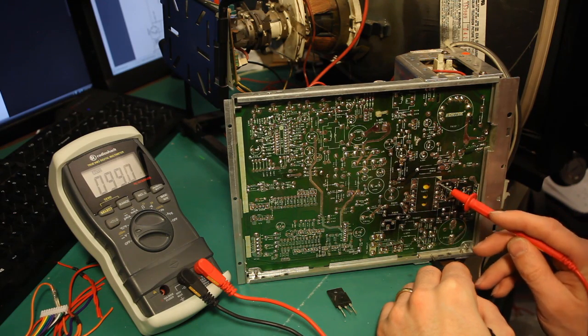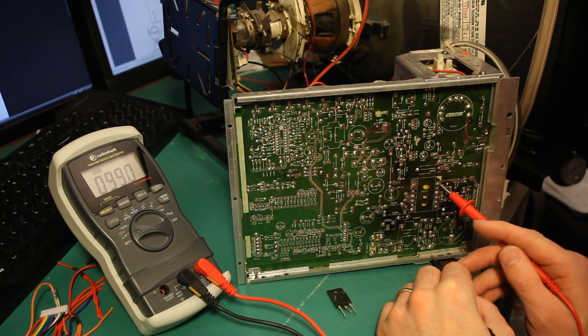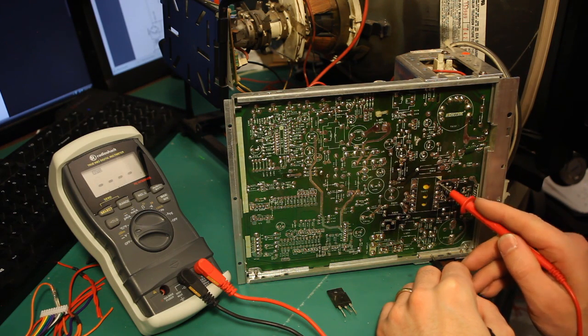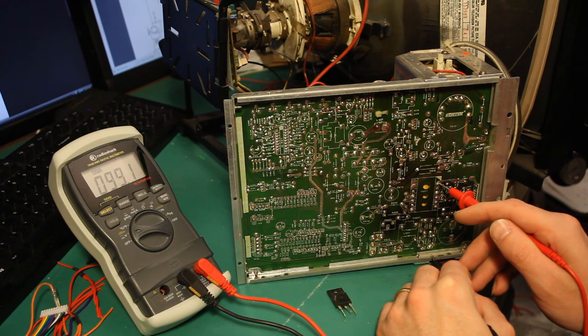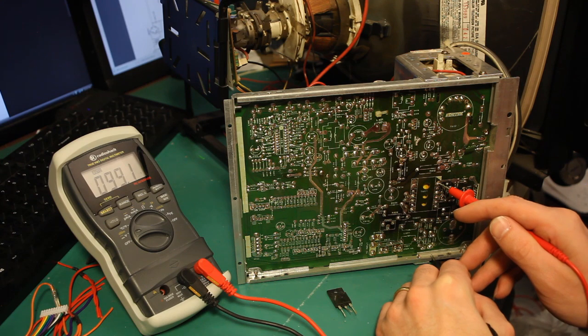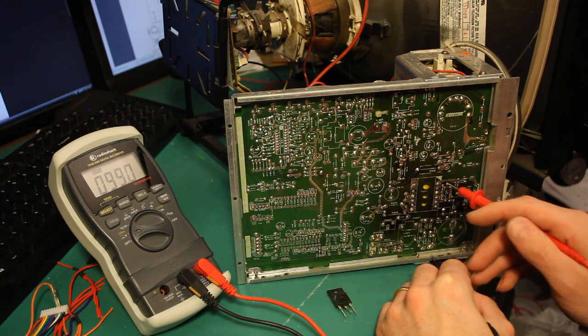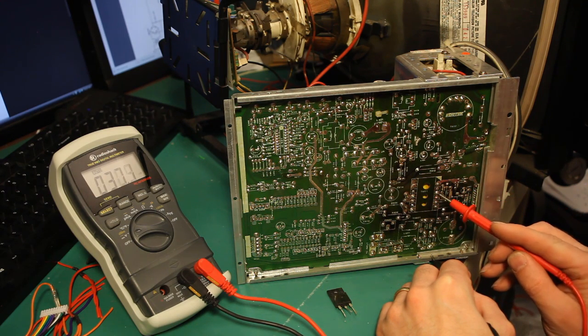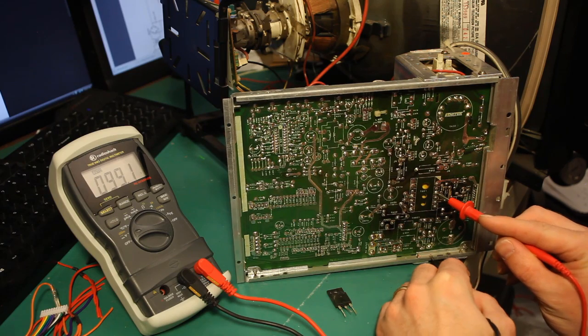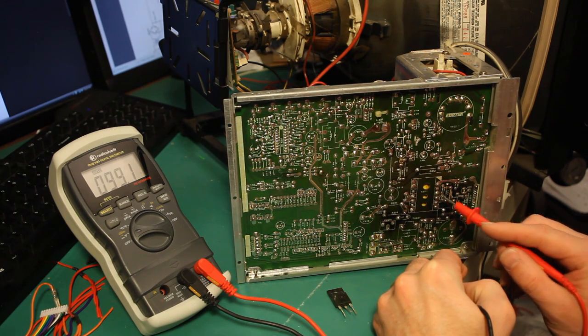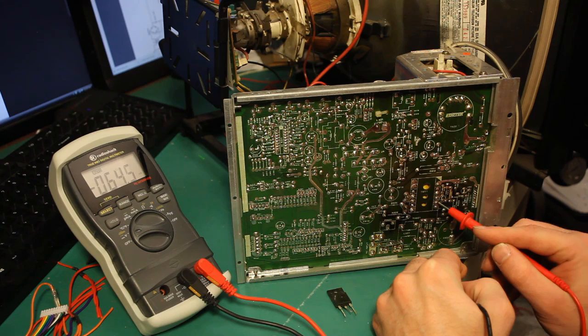Oh, there we got something. 99 volts. Okay, see that 99 volts? That's a weird number for me, because I would be expecting to see 170 volts or maybe half of that. And the reason 170 volts is so common is that is what 120 volts AC rectifies to, not under load.